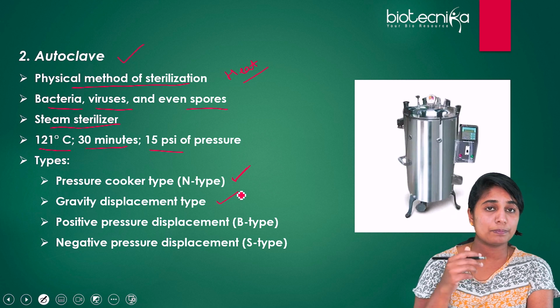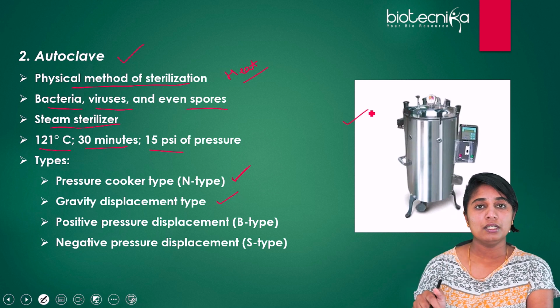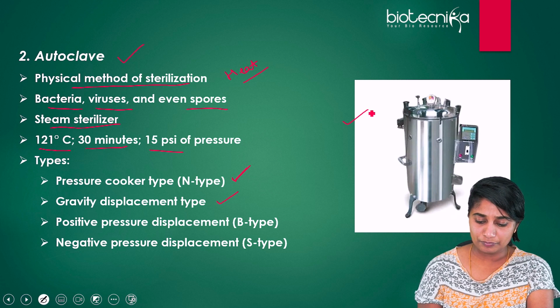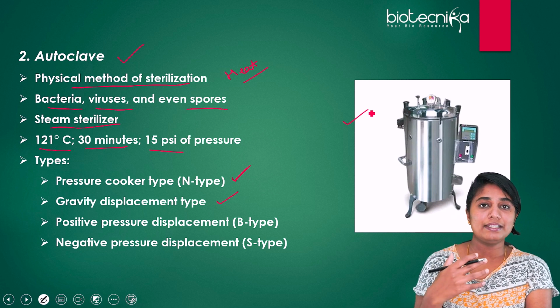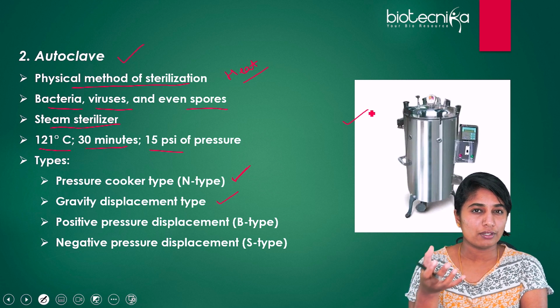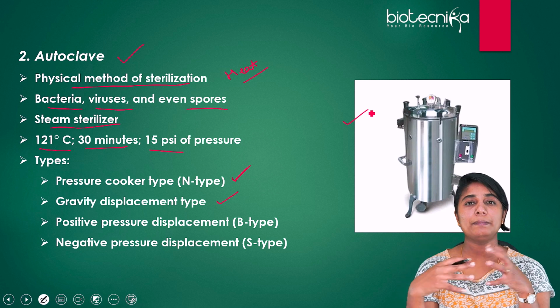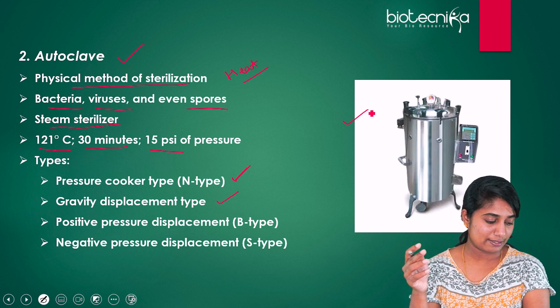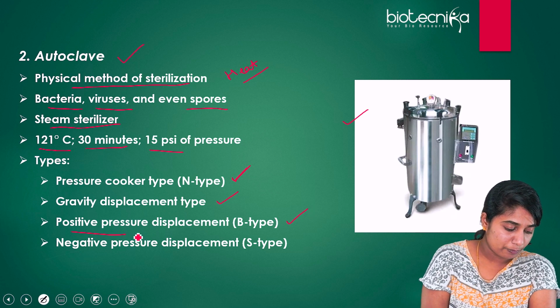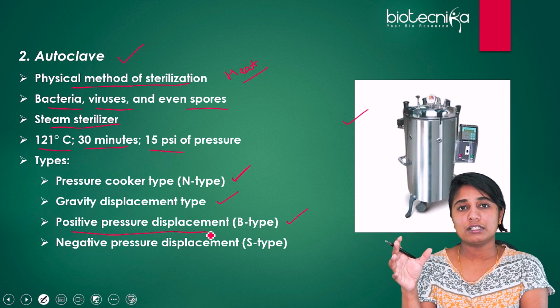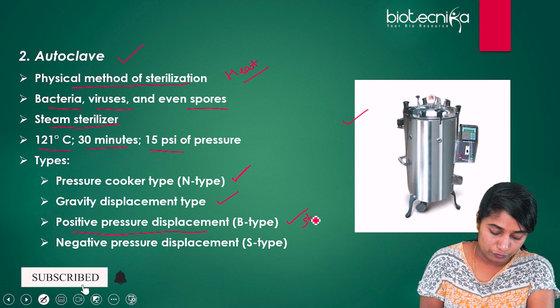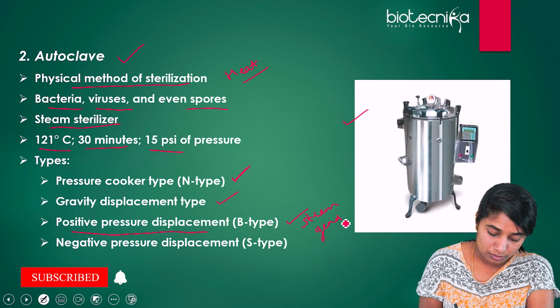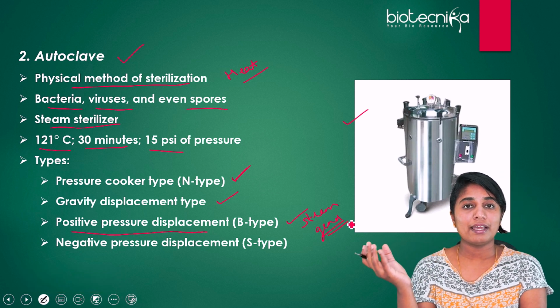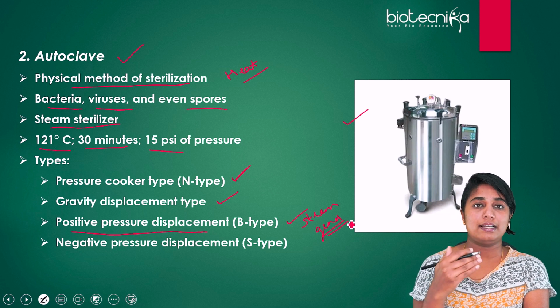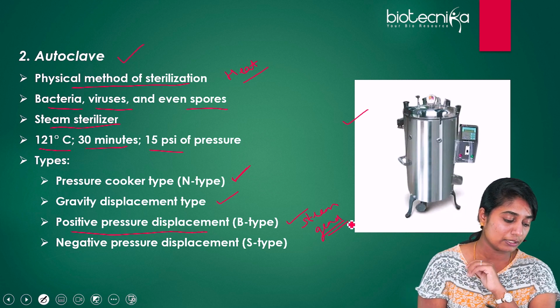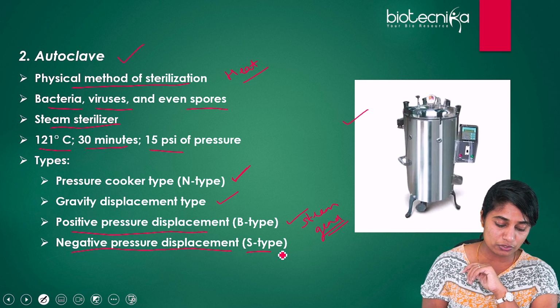The second is the gravity displacement type, which is seen here in the image as well. Here the steam is generated inside the autoclave machine because of the water that is present, and the steam keeps helping in sterilizing the medium that is inside. Next is the B type, or the positive pressure displacement. Here it has a separate steam generator as one of the units. In this steam generator, the steam is generated and this steam is then inflowed into the sterilizer where the sterilization actually happens. The fourth is the negative pressure displacement, also called the S type.